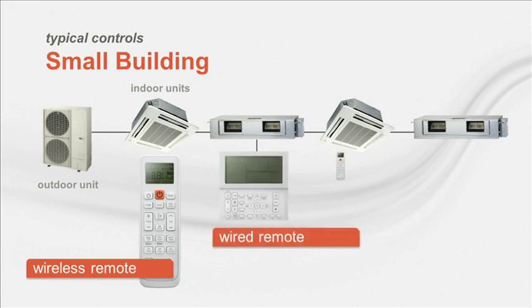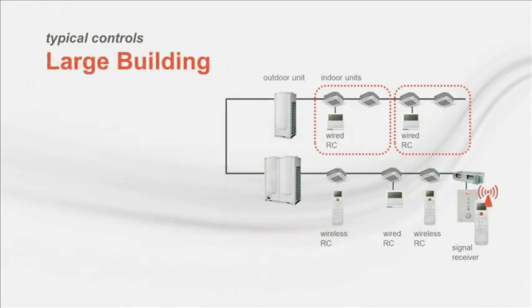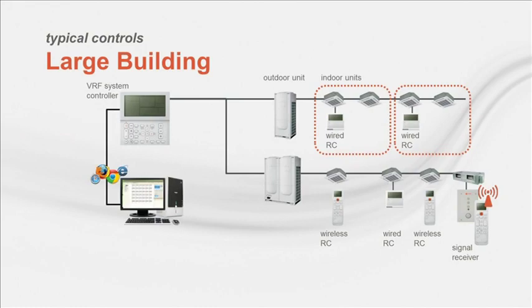Because they are out of sight, ducted indoor units are normally installed with a wired remote control. These wired controllers typically offer additional capabilities such as weekly scheduling, temperature limit setting, and error display. A single device can control multiple indoor units as a group. A wireless remote could be used with a hidden ducted unit if a remote signal receiver were installed. For larger buildings with several individual VRF systems, a VRF controller can be used. These controllers are typically capable of more complex scheduling, grouping of zones, for example by floor, and have the ability to override or limit settings in individual zones. The VRF system controller may add the capability for complex monitoring and error management, and also allows remote access through the internet.